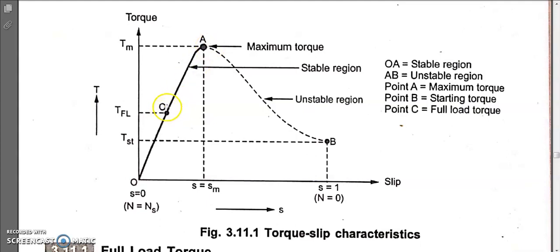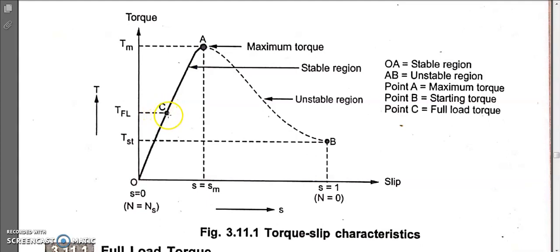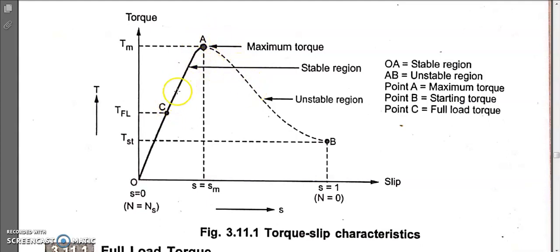Full load torque is always less than maximum torque, so always try to operate in the OC region. Don't cross from C to A because beyond C, temperature will exceed design limits. If temperature increases, insulation and windings may fail over a long period. Crossing point C occasionally for short-term operation may be acceptable, but long-term operation beyond C will deteriorate the insulation properties of the motor.